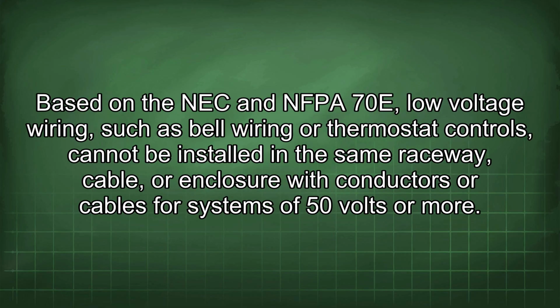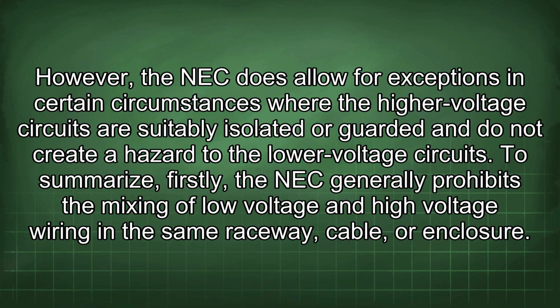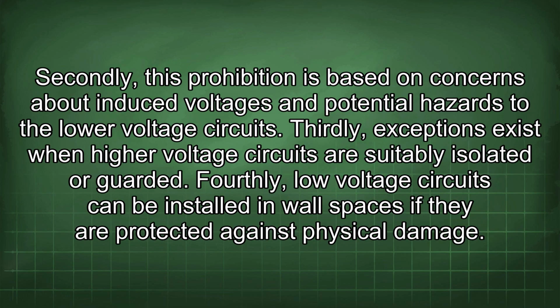Based on the NEC and NFPA 70E, low-voltage wiring, such as bell wiring or thermostat controls, cannot be installed in the same raceway, cable, or enclosure with conductors or cables for systems of 50 volts or more. However, the NEC does allow for exceptions in certain circumstances where the higher voltage circuits are suitably isolated or guarded and do not create a hazard to the lower voltage circuits. To summarize, firstly, the NEC generally prohibits the mixing of low voltage and high voltage wiring in the same raceway, cable, or enclosure. Secondly, this prohibition is based on concerns about induced voltages and potential hazards to the lower voltage circuits. Thirdly, exceptions exist when higher voltage circuits are suitably isolated or guarded.